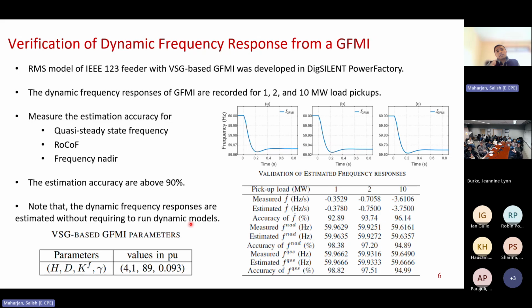And this same estimate was made by the constants we defined above, okay? And we found that the constants we defined were able to measure those dynamic frequencies to an accuracy of above 90%. So for the planning problem, I think this accuracy is acceptable. And so with this verification, we ensured that those dynamic frequency response equations can be used in the problem without requiring you to run the RMS simulation to measure these dynamic frequencies.